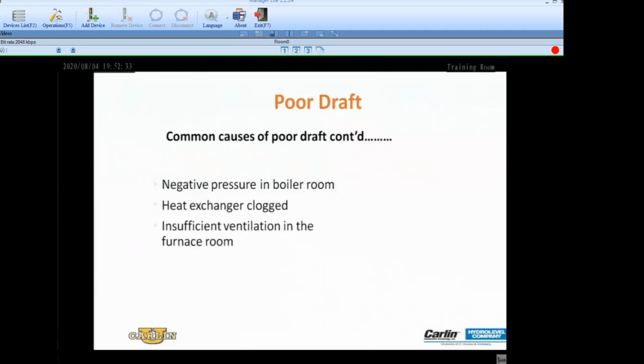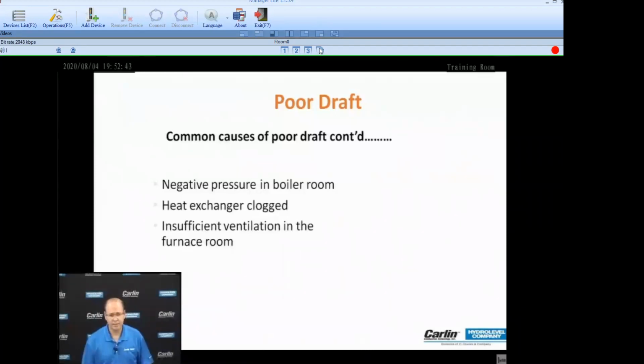Heat exchanger clogged. Common thing for technicians to do. The heat exchanger's clogged. What do? I don't want to clean this. Hey, put a smaller nozzle in there. Small nozzle takes away the back pressure and they move on. Let the next guy worry about it.